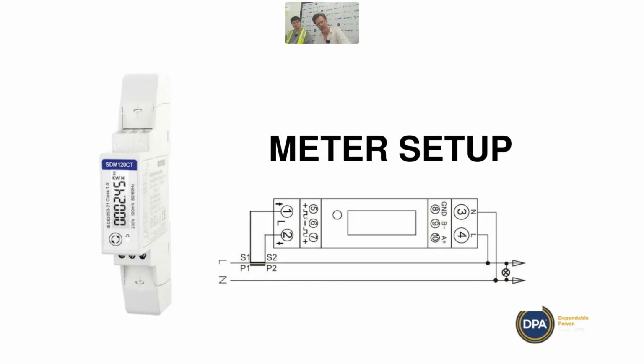You've got to power the meter, so we've got neutral and active up top here in ports 3 and 4. I'd recommend putting your wires into that before mounting it on the DIN rail in the main switchboard, because it's quite fiddly and the screws are a bit funny, and it can be a real pain once it's all in there with the rest of the mess. So put those wires in first, then put the meter in place.